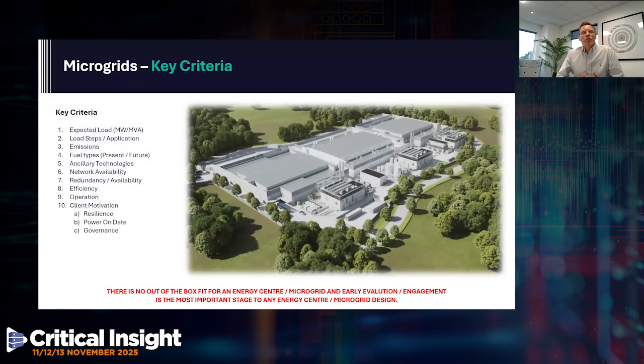So the key criteria we think about when looking at a microgrid are: expected load in megawatts and MVA, the load steps - the application of load to the microgrid, the emissions from the microgrid, the fuel types, the ancillary technologies like carbon capture and trigen, network availability - do we have 10 MVA of network connectivity that we can use to help the grid, and can we use that 10 MVA to balance the microgrid, the efficiency, the operation, and one of the key ones is the phasing of the microgrid.